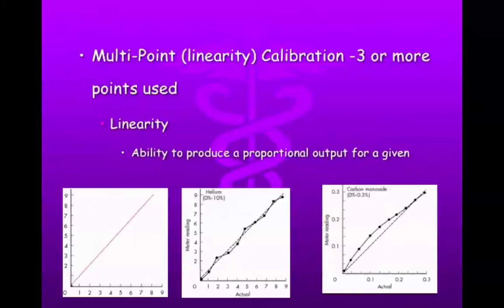Now you have an example in the box to the right that shows you one that's swinging way out of linearity. If it exceeds that particular setting of a high or a low, it's no longer linear. In this case, this one is not linear because it swung way out of the linear line and then eventually came back in again. This could be a problem and something that you want to look for. Sometimes as you're doing these calibrations, you'll start seeing a trend of something starting. It may still be within the right range, but it's trending outside of that range. You want to look for those things because those are signals.